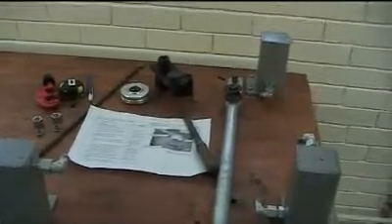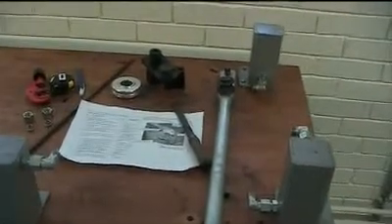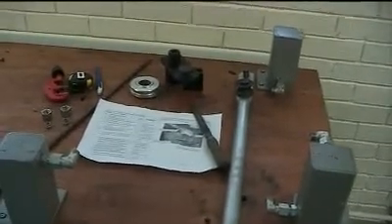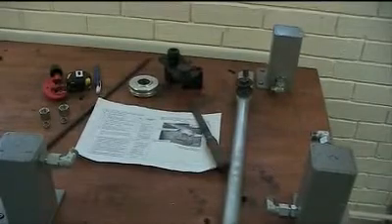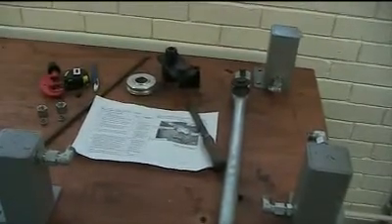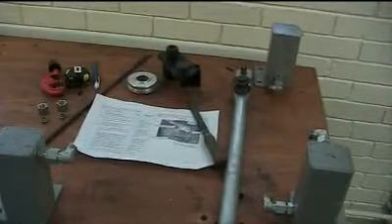To complete this task you'll need the following equipment: one standard operation procedure to help you complete the task, one length of 10S hydraulic pipe 650mm long, two 10mm compression nuts, two 10mm olives, a hydraulic pipe cutter, tape measure, a pencil, hydraulic pipe bender with 10mm forming die, and one flat file.